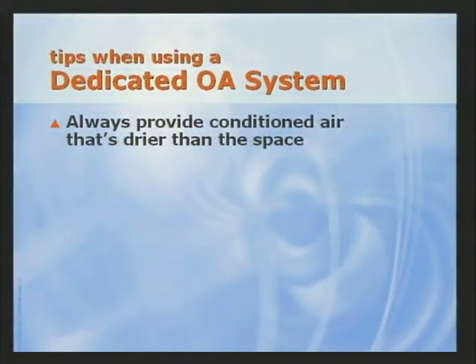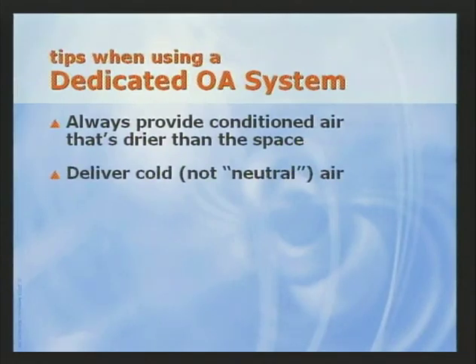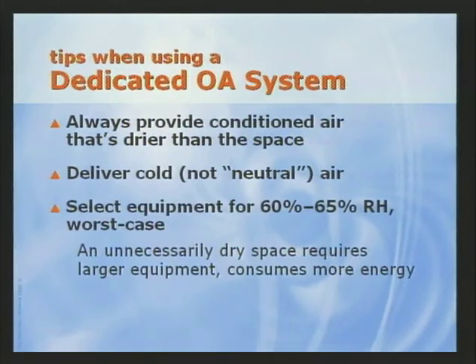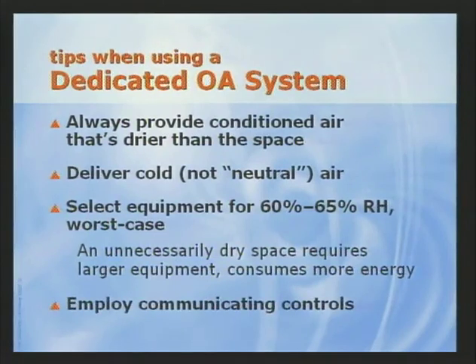Now, we produced a broadcast in September 2001 on the subject of dedicated outdoor air systems. And some of the key points from that broadcast were, first, always deliver conditioned outdoor air that is drier than the space, dry enough to also offset the space latent loads. Now, this adequately limits indoor humidity without the need for additional dehumidification enhancements in the terminal units. Second, deliver cold conditioned air whenever possible. Neutral air increases the capacity required from the terminal units and typically requires reheat at the dedicated outdoor air unit. For most school applications, select equipment to limit space relative humidity between 60 to 65% at worst case conditions. Now, designing for lower indoor humidity levels is certainly possible, but requires larger equipment and increases energy consumption. Finally, take advantage of communicating controls to provide a better overall system.